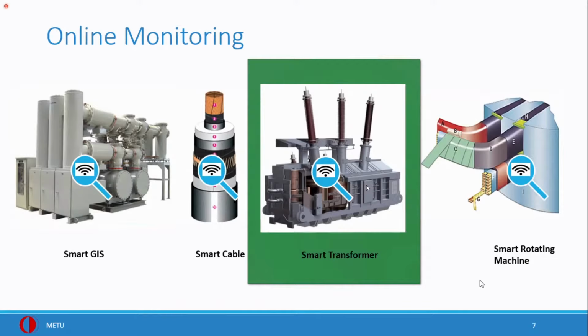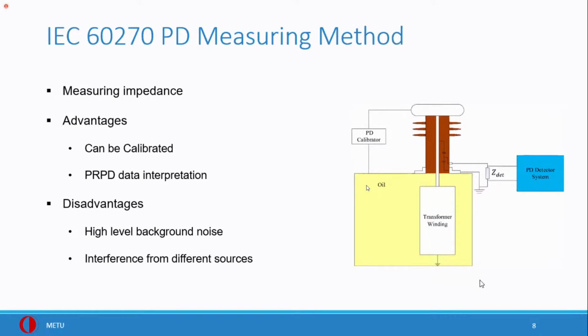Insulators encounter lots of problems and are the main source of problems in power system equipment. To monitor their situation, we had the idea from 4 or 5 decades ago that the best method is partial discharge measurement. When they have problems, they start producing partial discharge signals.